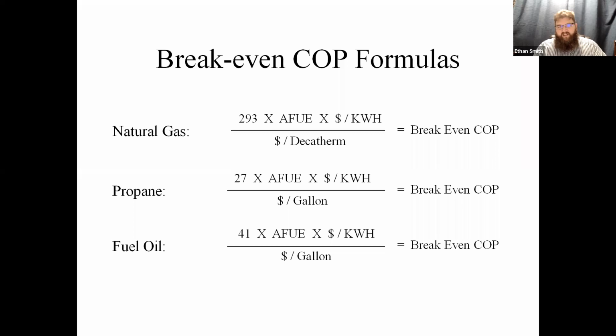These are the formulas for that, guys. So for natural gas, we've got a constant of 293. We multiply that by the efficiency of the furnace. So this would be 96.8 or 92 or 85 or whatever the efficiency level of your furnace is, just in whole numbers. We multiply that by the price per kilowatt hour. This is in dollars, so if it's 8 cents a kilowatt hour, it's 0.08. And then if we're going to compare that to natural gas, we divide all that by dollars per decatherm.